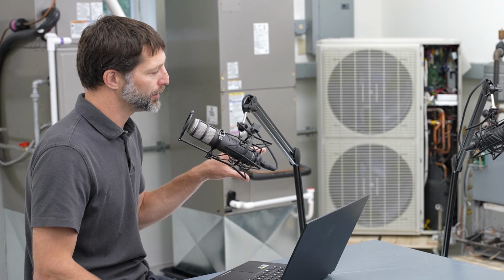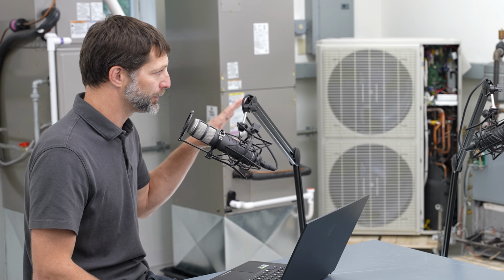If you're using an aftermarket ECM motor, you're going to also want to pay special extra attention to what speeds it's running at, and definitely you want to be measuring the airflow to make sure you have the correct airflow during air conditioning and heating mode. That initial ECM motor is programmed for that specific model. You can't just take one that came out of, say, a 5-ton unit and put it into a 2-ton unit. It's not going to work properly, and you just need to be aware of that. Yep. And most of those instructions are pretty well done. They have step by steps. So just take some time, read through it, follow the steps, and it's not nearly as scary as it sounds.